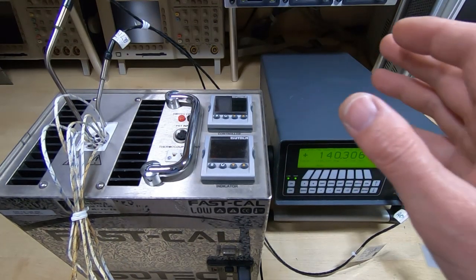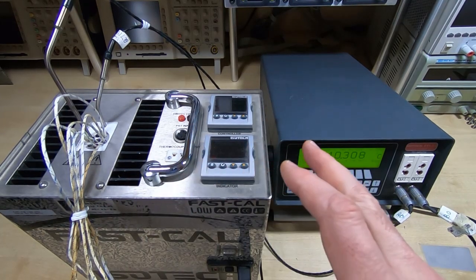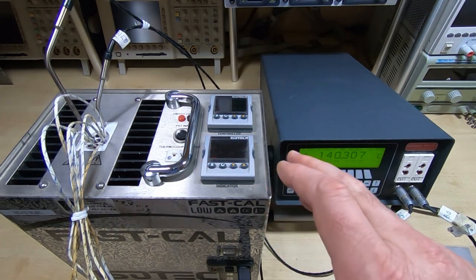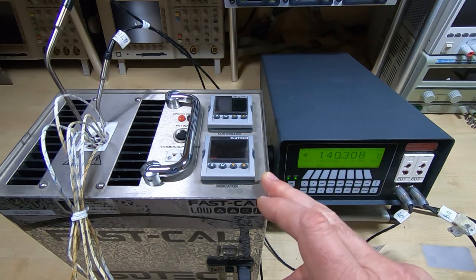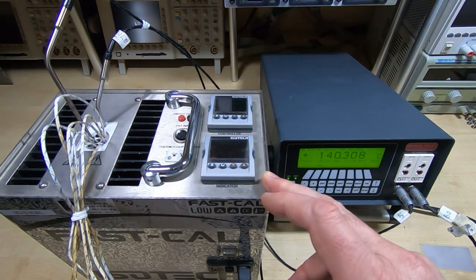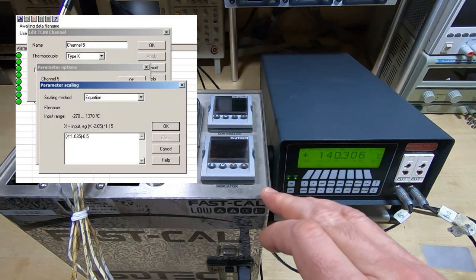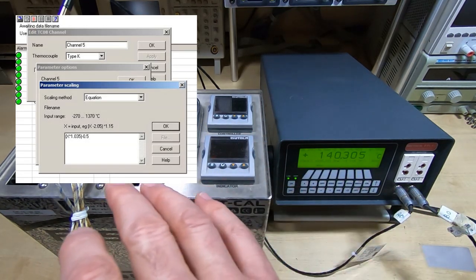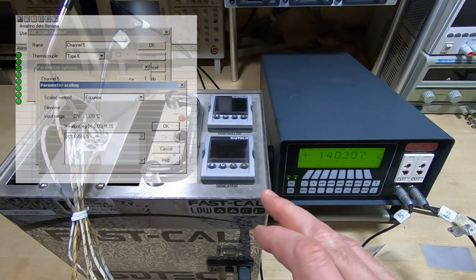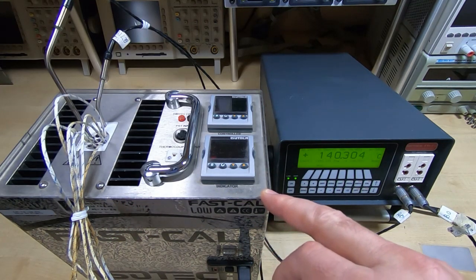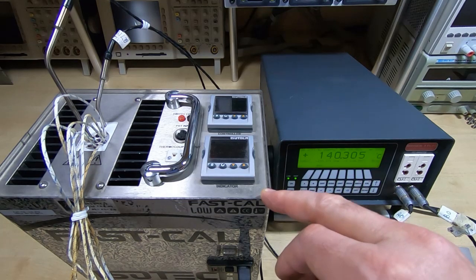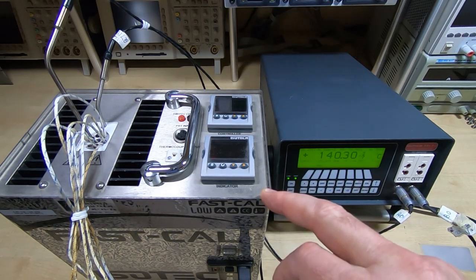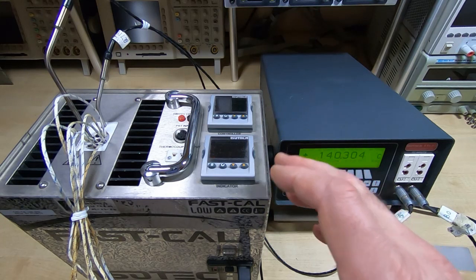So the final part of the process, once the data has been captured and all the errors have been determined, the next step is to create a correction algorithm or correction formula for the individual probes. So there's an example of that here. You can see it's just a simple formula that's used based on the errors that have been detected, and the purpose, of course, is to correct the error across the entire range of the probe. It varies slightly from probe to probe, of course. That's the point of this process.